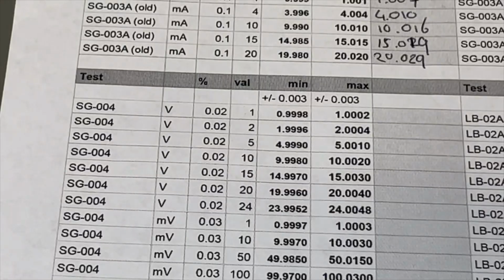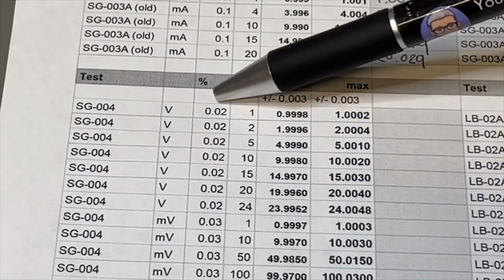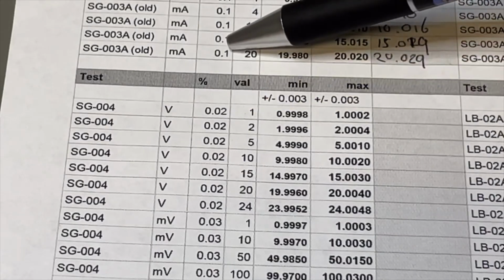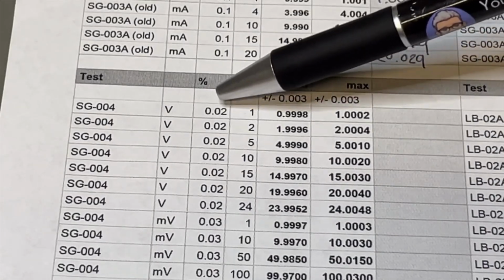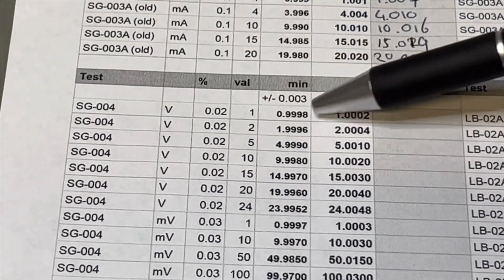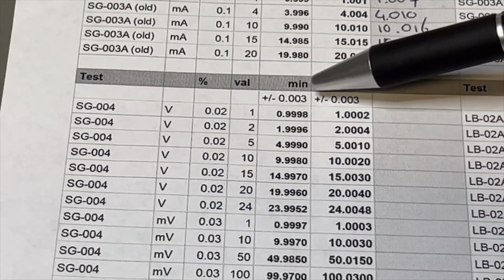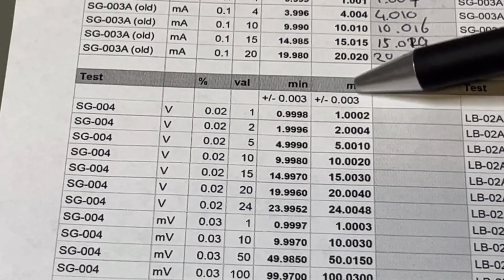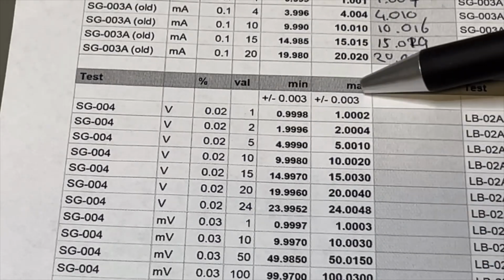This one is probably calibrated better and has a better ADC inside to generate a more precise voltage, because here they specify instead of 0.1 we have a 0.02. That means it should be within this, but then added this digit, and instead of a 5 it is a 3 now.